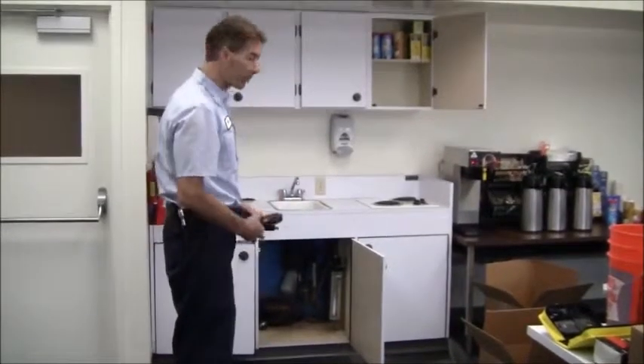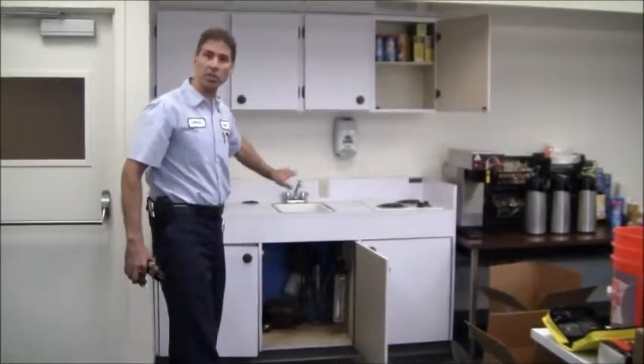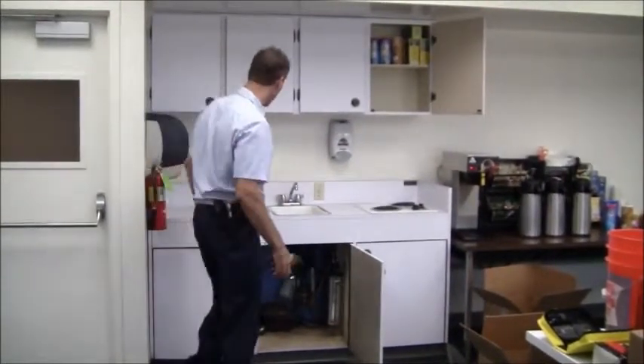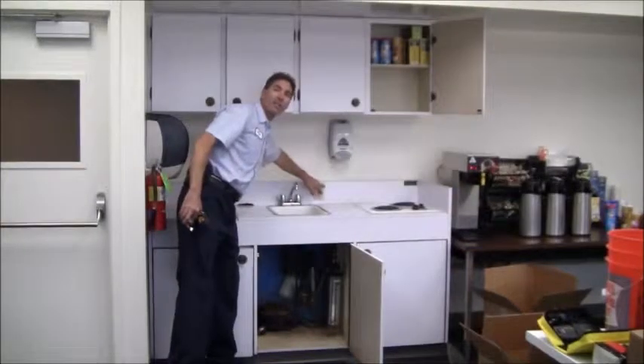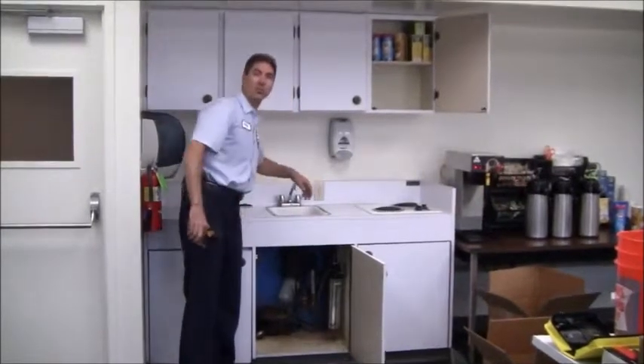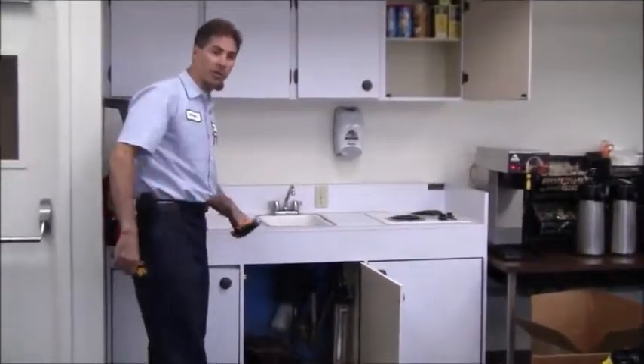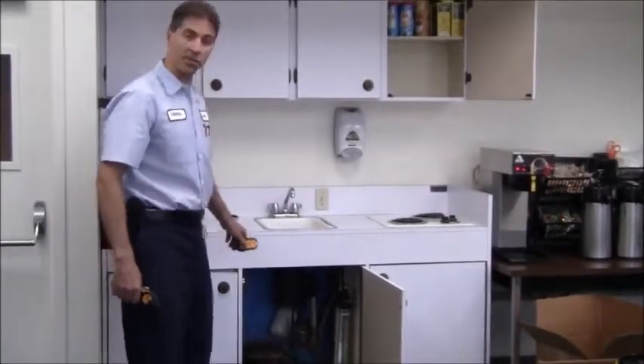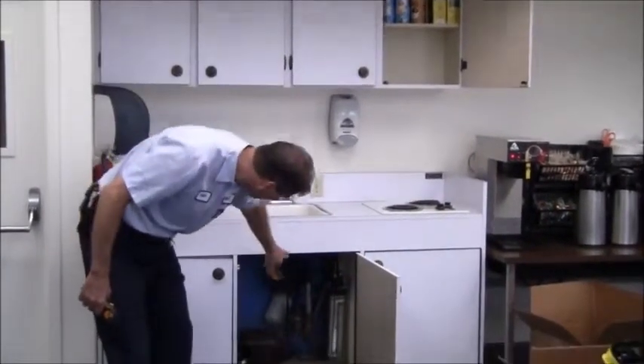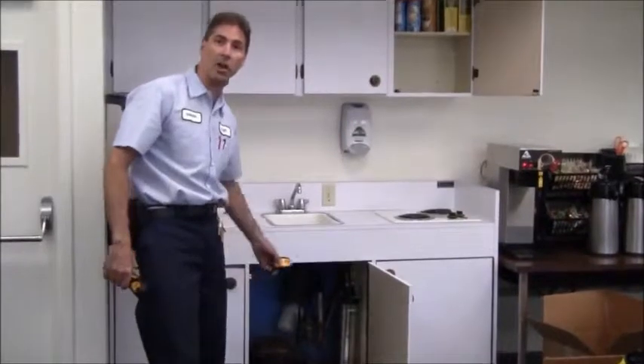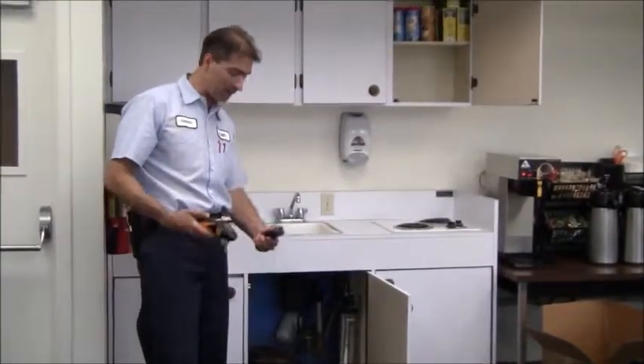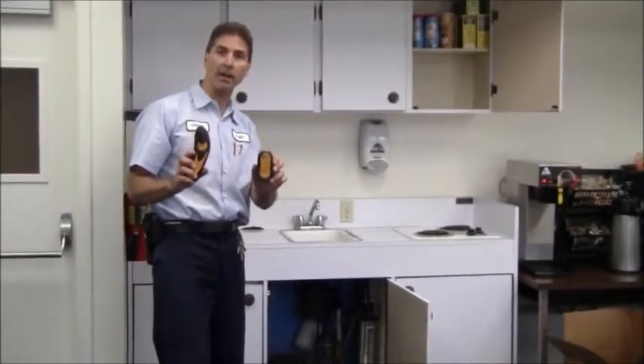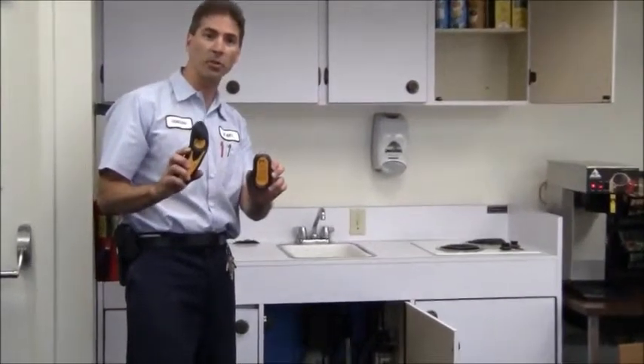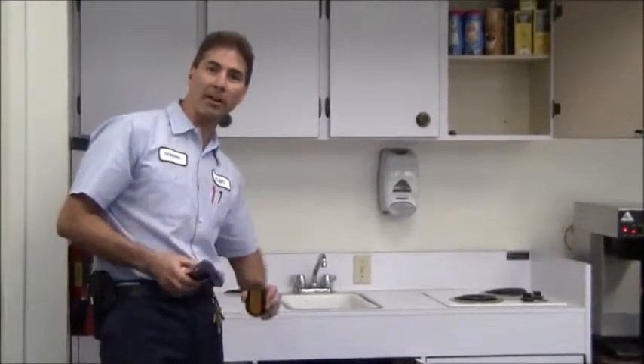Okay, so the first thing I want to do is make sure there's no electricity or water in this station. Right now, that's a garbage disposal with power going to it, and I need to find that circuit breaker because it's attached to the side wall of the panel here. It's not labeled, so how am I going to do that? I'm going to use my circuit breaker finder to find that circuit breaker and shut it off.